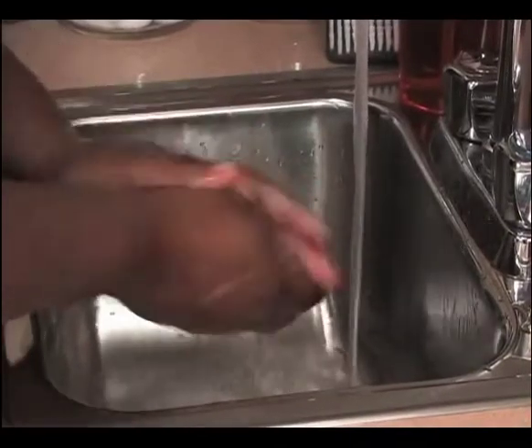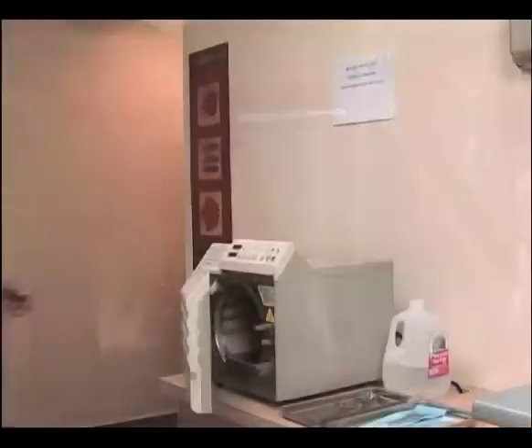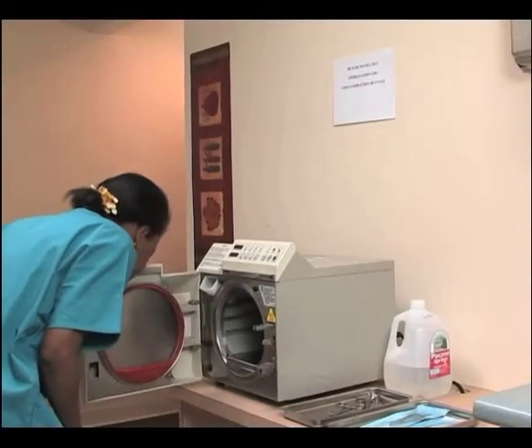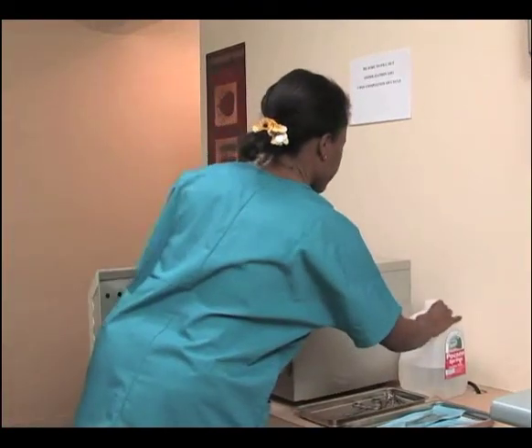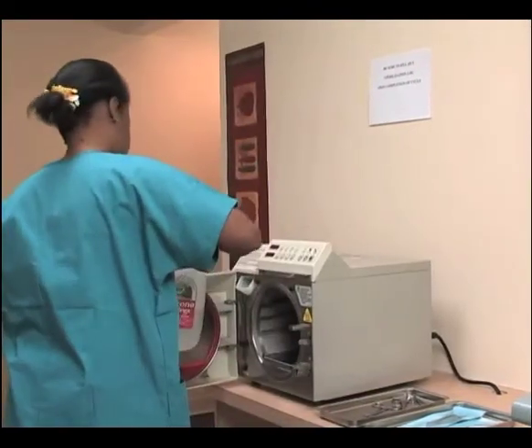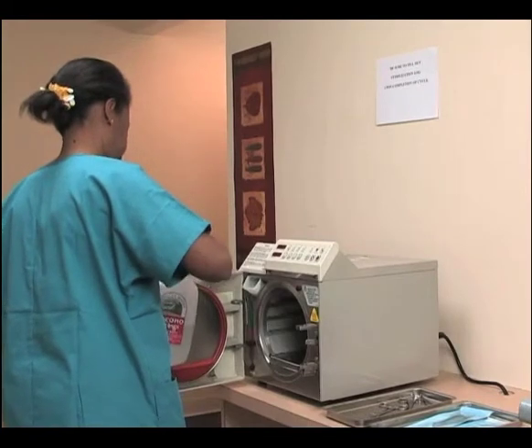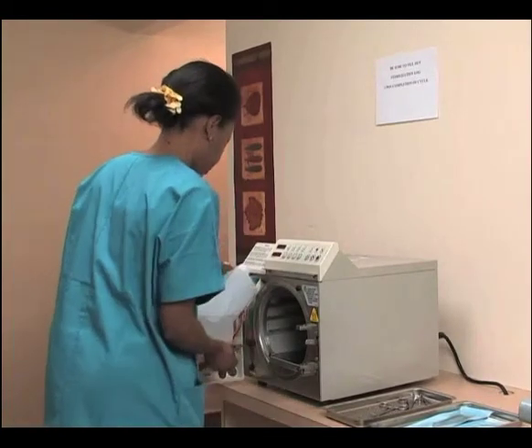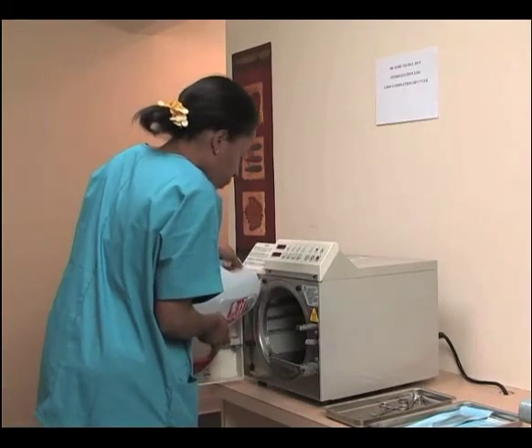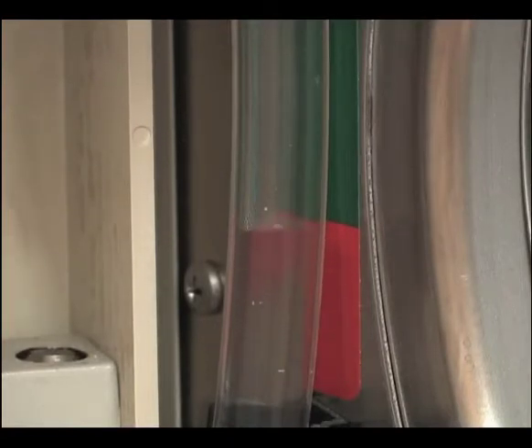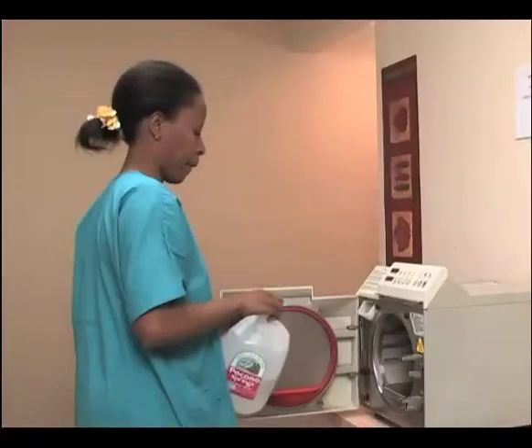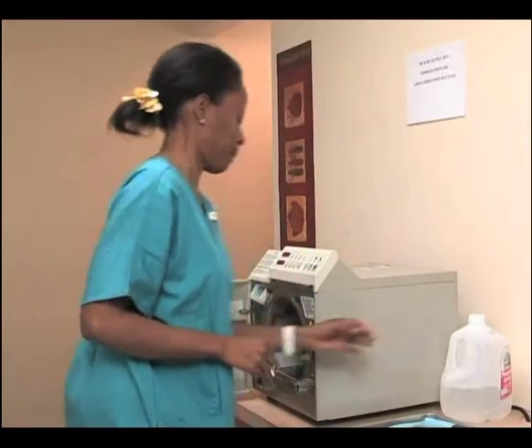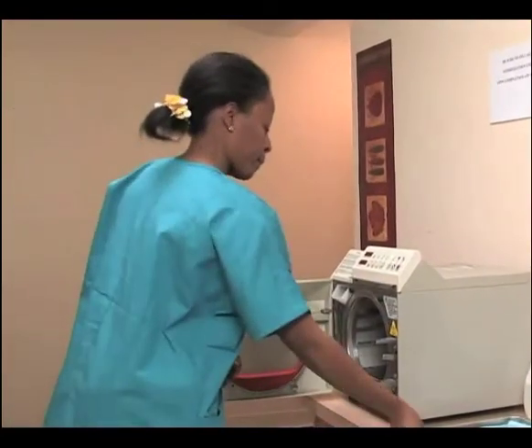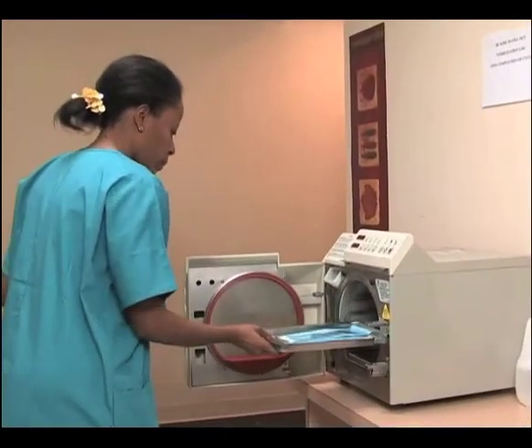Begin by washing your hands and assembling materials. Check the level of distilled water in the autoclave reservoir and fill as necessary. The water produces steam for sterilization. Air pockets, created when the autoclave reservoir is empty, can reduce the temperature in the autoclave and prevent total sterilization. Using distilled water prevents mineral corrosion inside the autoclave that might block the air exhaust valves.